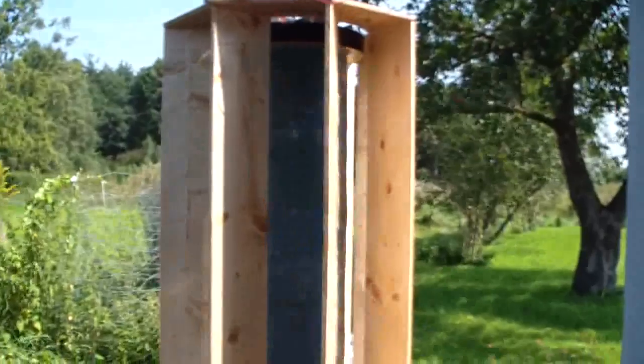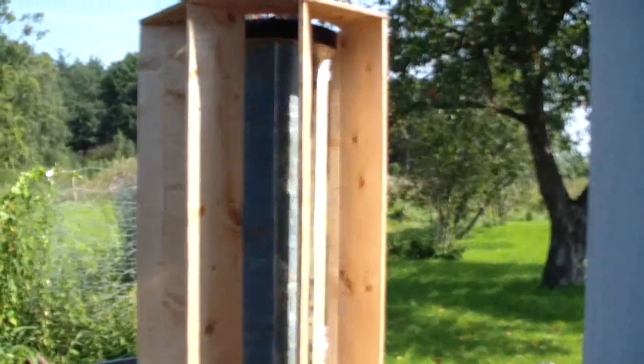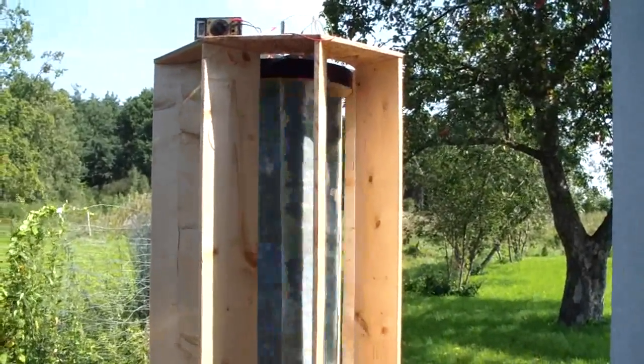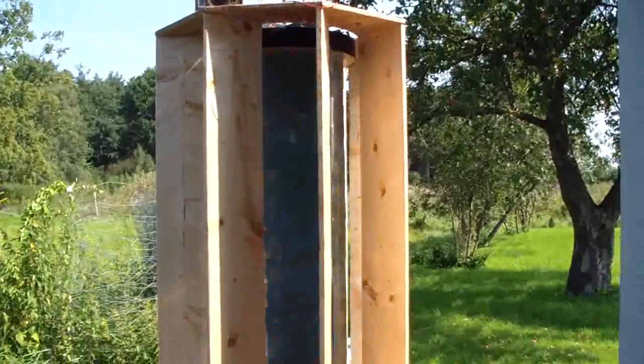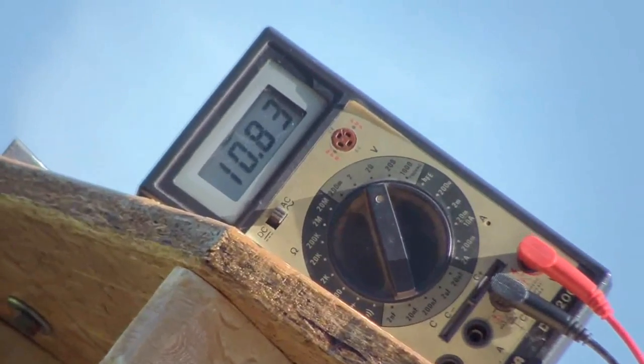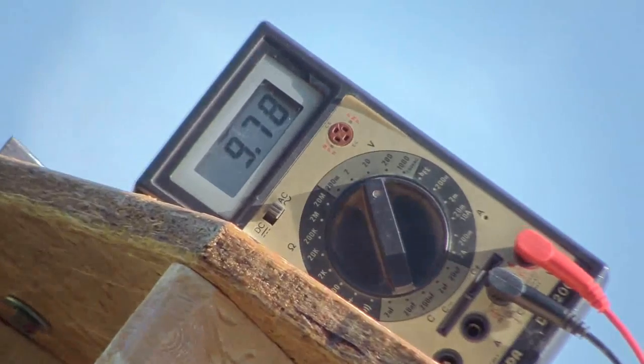which is about 1.4. And the other way around, when you want to have the peaks at 13.5V, you divide by the root of 2 and you get something about 9.6V. So this generator would start to load a battery at about 9.6V. Of course you can't charge a battery with alternating current — you have to rectify it first. Anyway, you see that even this 9.6V is reached not that often.